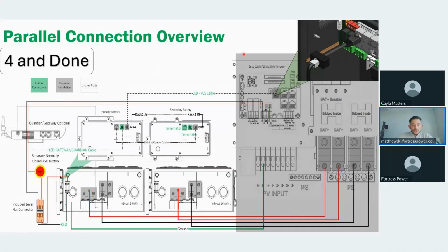And then this would be sort of a parallel overview of how you would basically communicate the batteries if you were in parallel, starting with the electrical cables, right? Each electrical cable would go into the 2 battery ports of the MV Duo or MV12. In the case of an 8K or 10K, then you would just parallel both bus bars to each other. And then from there, you would run it to the inverter terminals, since the 8K and 10K only have 1 battery terminal. Then you would connect the battery to battery communication cable from eVault to eVault.